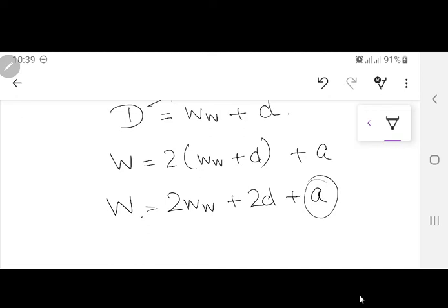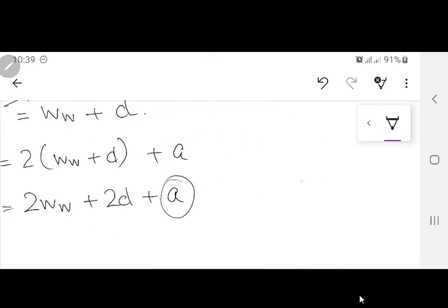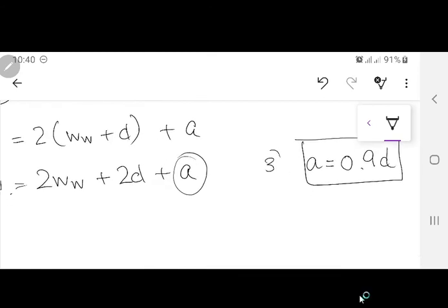So now for this you have to have a table over here. Over here A is equal to, this is written actually in this one, for a 3-step core they have written it approximately, this is equal to 0.9 D. Because this is the 4-step core, for a 4-step core it will be different, but I am using this one since I don't have it. Let me see on the table if this value is given. For a 4-step core, 0.92 is given. Okay, just let's use 0.9 or 0.92 D or whatever. This is for the 3-step core. For a 4-step core, let me call it 0.92 D, just for example.